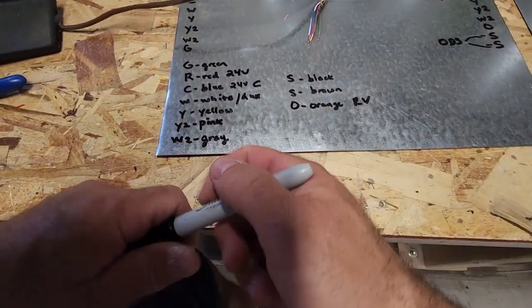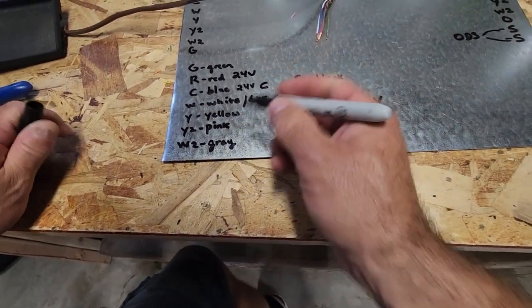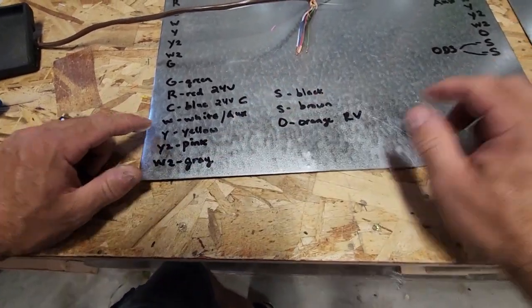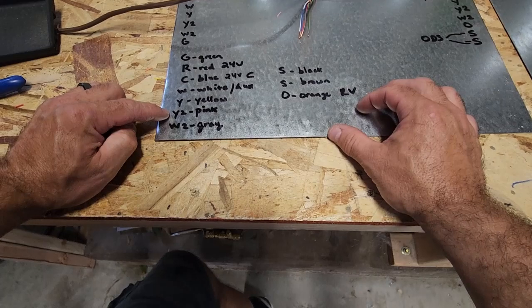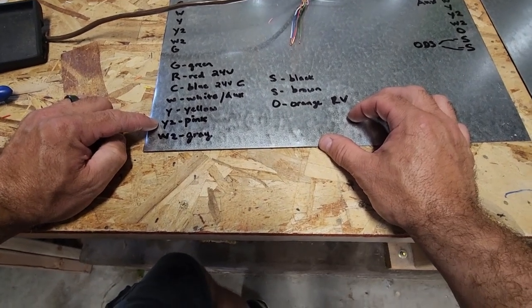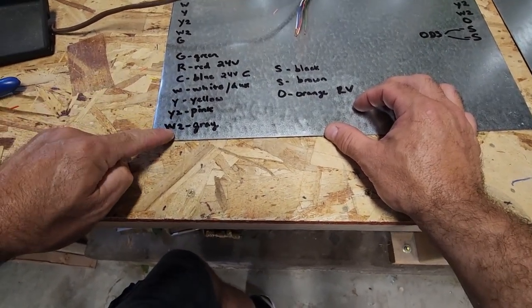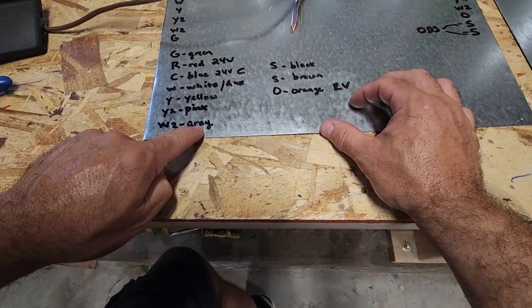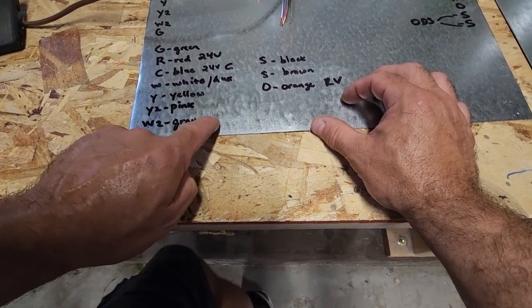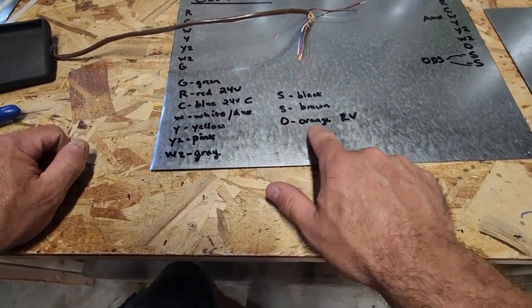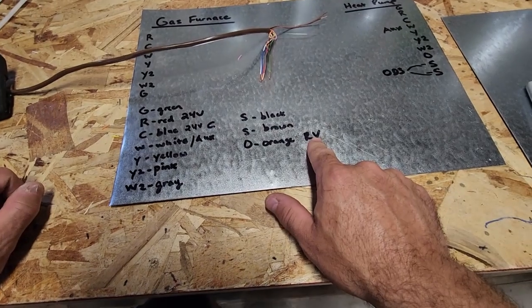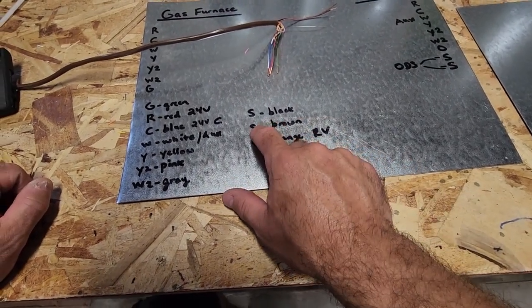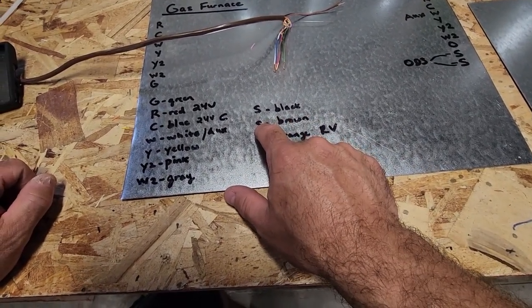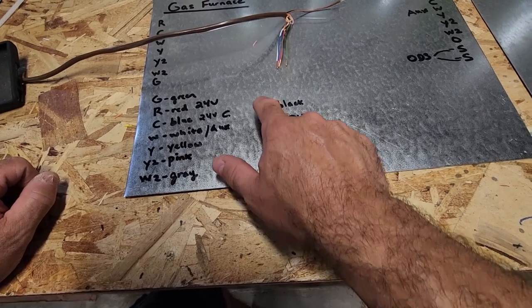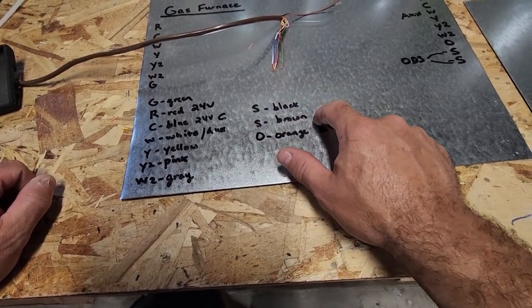Y is yellow. That's always going to be first stage. I want it right there. I don't have room. First stage condenser. Y2, pink, second stage condenser. W2, I use gray, and that's always going to be your second stage heat. And then you have O is going to be orange for your reversing valve and a heat pump. And then your 2 outdoor sensor terminals. S terminals usually on heat pump thermostats. I like to use black and brown.